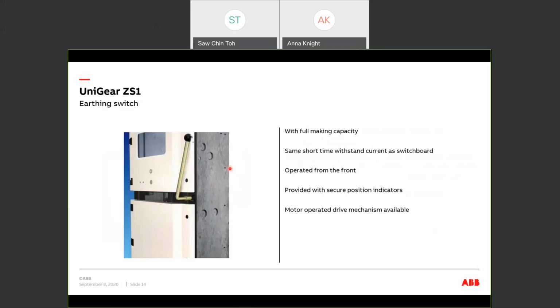All the panels will be equipped with an earthing switch for cable earthing. We also have the option to install an earthing switch on the bus bar for bus bar earthing. The earthing switch will have the same full making capacity and short time rating as the switchboard, meaning, for example, for a 31.5 kA rated board, you'll have the same 31.5 kA rated earth switch with a making capacity of 80 kA.